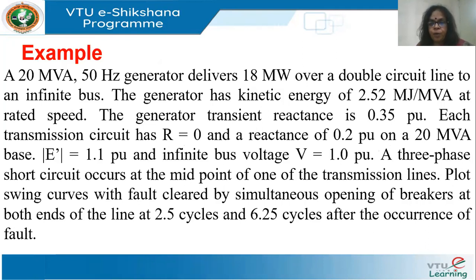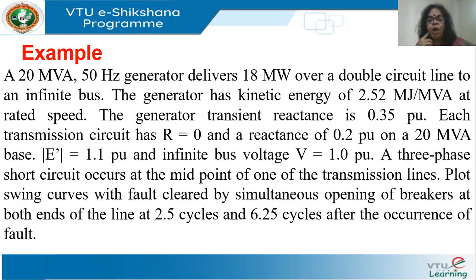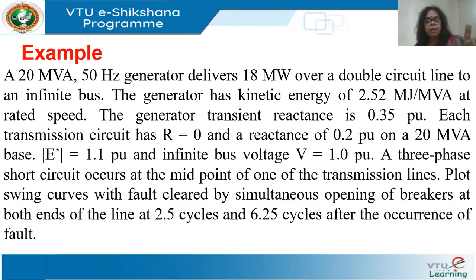Let's take up an example: a 20 MVA, 50 Hz generator delivering 18 MW over a double-circuit line, with H = 2.52, generator transient reactance of 0.35 per unit, resistance neglected. Each line has 0.2 per unit reactance, generator voltage 1.1 per unit, and infinite bus voltage 1 per unit. A three-phase short circuit occurs at the midpoint of one transmission line. Plot swing curves with the fault cleared by simultaneous breaker opening at 2.5 cycles and at 6.25 cycles.